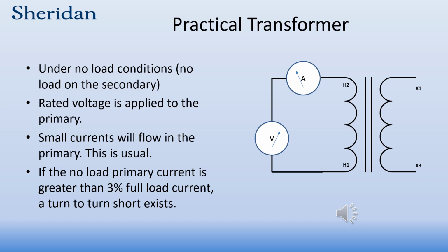If the no load primary current, however, is greater than 3% of full load current, what really should be suspected or looked for is a turn-to-turn short in either the primary or the secondary windings. This is a fault. This may not show up in the Megger test, but does show up when you do this no load voltage test.